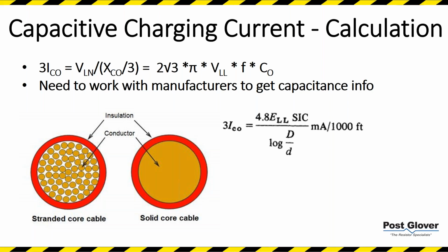There's a lot of nuance, and part of it is you can do calculation. Here's your basic formula: 2 times square root of 3 pi, times line voltage, frequency, and zero sequence capacitance. On some of your equipment, like wire, for example, it is fairly simple. We'll talk about that in a second. But for some of your equipment, you may need to work with manufacturers to get the capacitance info. It may not be that easy to figure out. So the calculation may or may not be possible or easy. But I would say with wire, it's almost always easy.